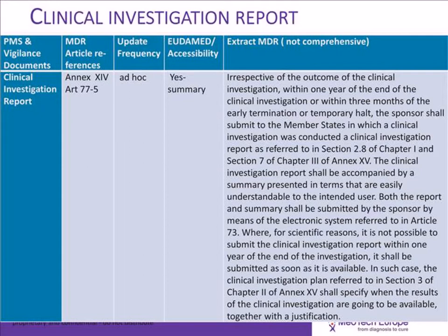The first one is the investigation report itself, which need to be produced in the 1 year following the completion of the clinical investigation. There are also provisions for an early production of this report in case the study is stopped on safety grounds.